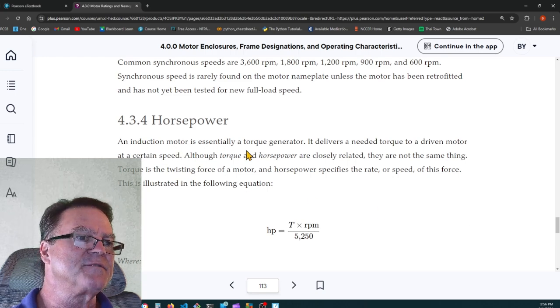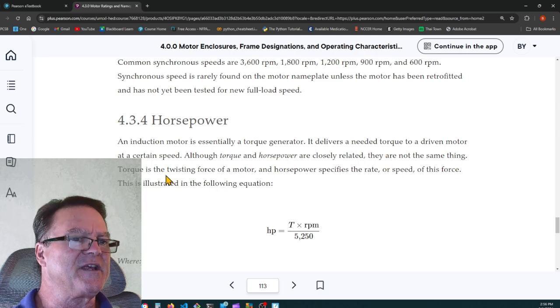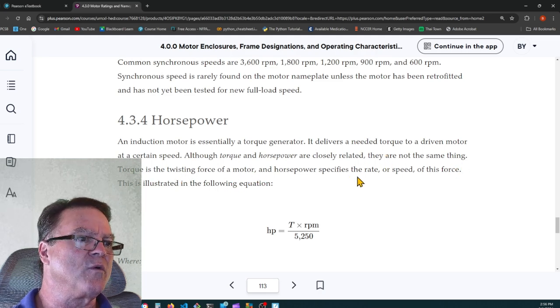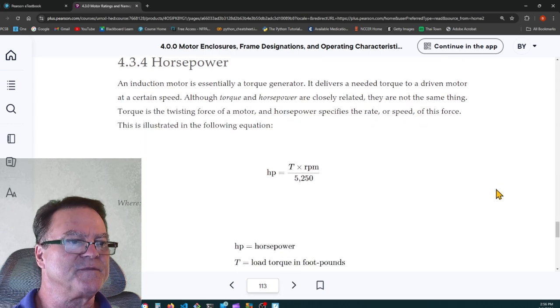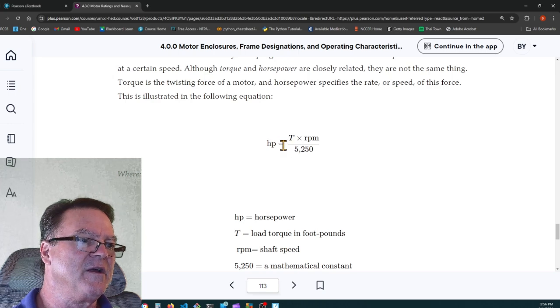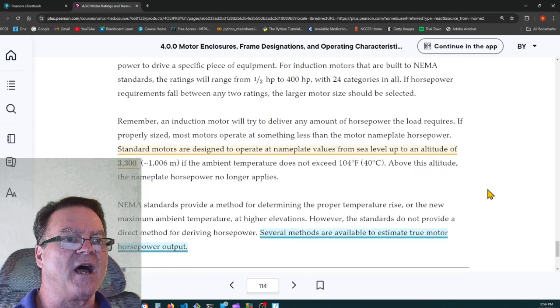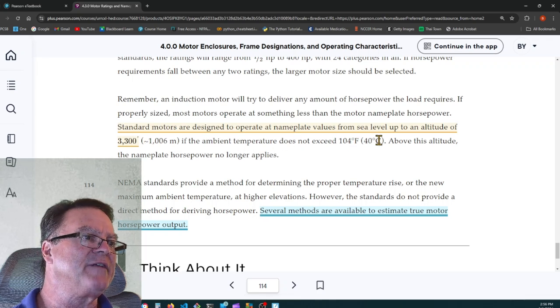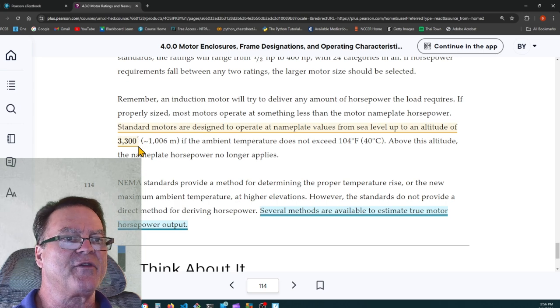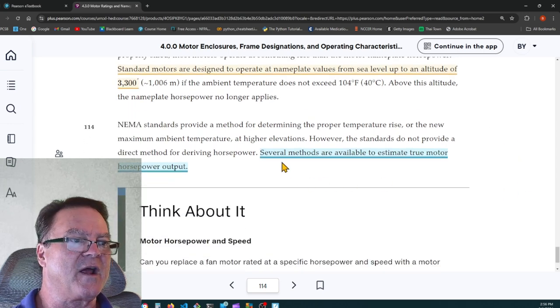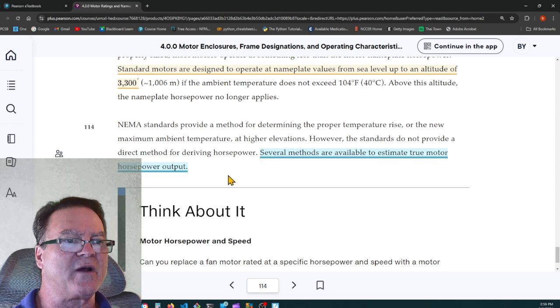Horsepower. An induction motor is essentially a torque generator. It delivers a needed torque to a driven motor at a certain speed. Although the torque and horsepower are closely related, they're not the same thing. Torque is the twisting force of a motor, and horsepower specifies the rate or speed of this force. So they give you a formula: load torque in foot-pounds times the rotations per minute divided by 5,250. It's a mathematical constant, and that equals the horsepower. Here's a highlight. Standard motors are designed to operate at nameplate values from sea level up to an altitude of about 3,300 feet. So here's another highlight. It says several methods are available to estimate true motor horsepower output.